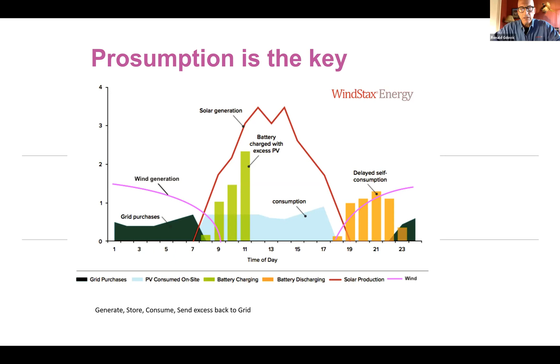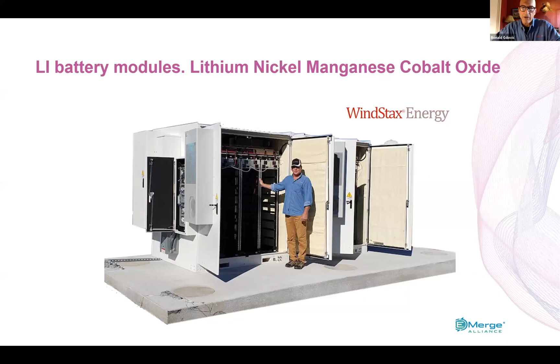So we are generating wind and solar in the 900 to 1,000 volt range, storing it, and then stepping it down to 380 volt DC. For this customer, you can see the high bay lighting and office fixtures are also running on DC, stepped down further to 24 volt DC, which I'm sure you'll hear more about shortly.